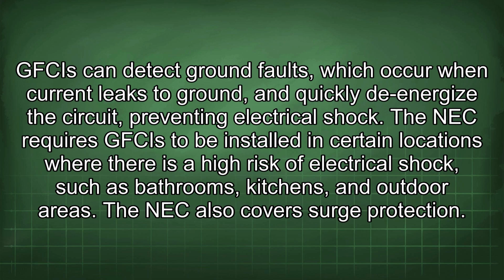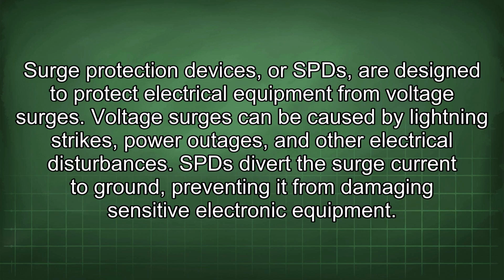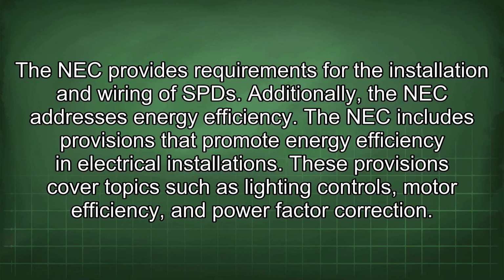The NEC also covers surge protection. Surge protection devices, or SPDs, are designed to protect electrical equipment from voltage surges. Voltage surges can be caused by lightning strikes, power outages, and other electrical disturbances. SPDs divert the surge current to ground, preventing it from damaging sensitive electronic equipment. The NEC provides requirements for the installation and wiring of SPDs.